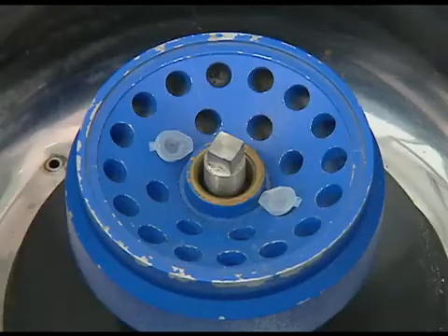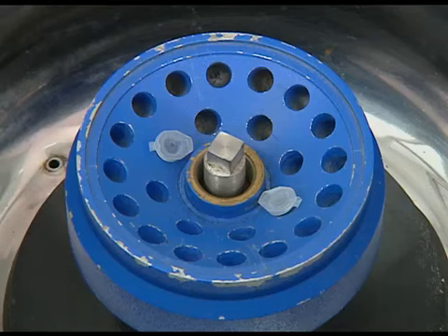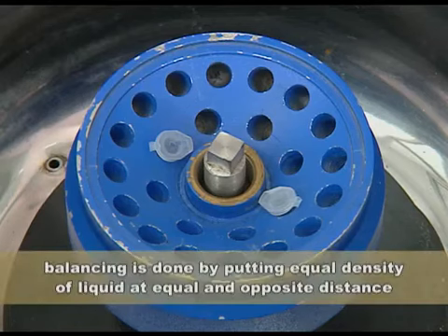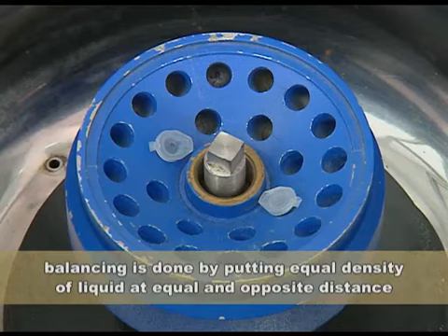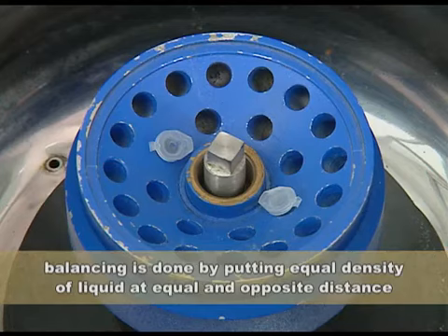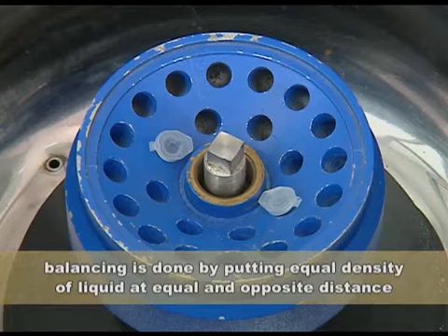Another important criterion is the balancing of the device. Balancing is done by putting the Eppendorf or centrifuge tube at equal position, that is exactly opposite position, and also the density of the sample, or the amount which is taken in the centrifuge tube, should be approximately equal.